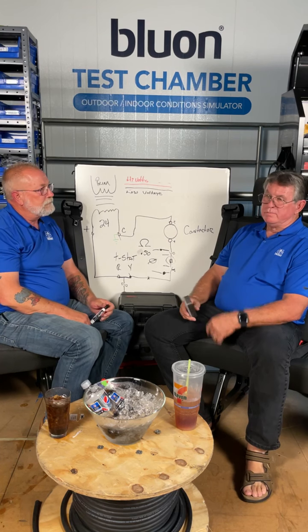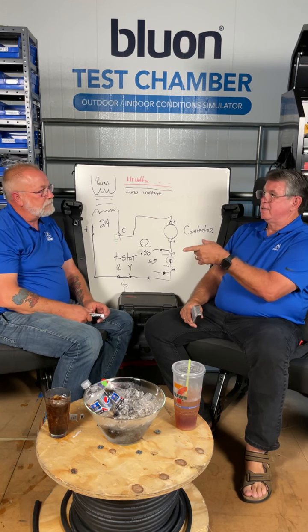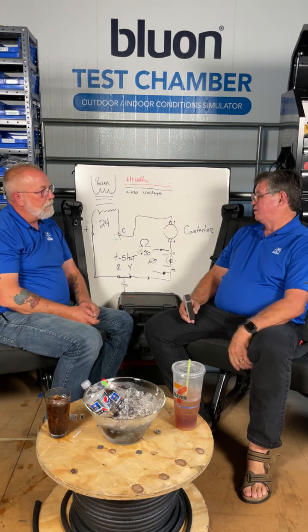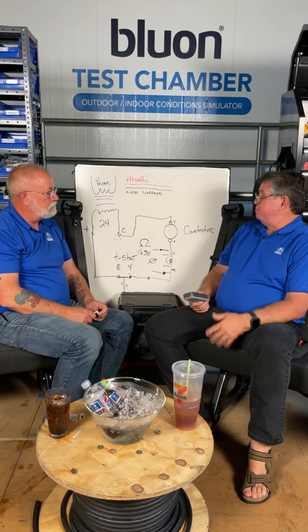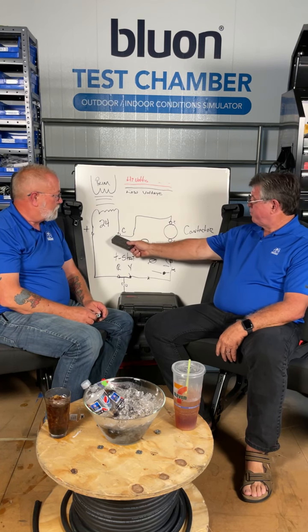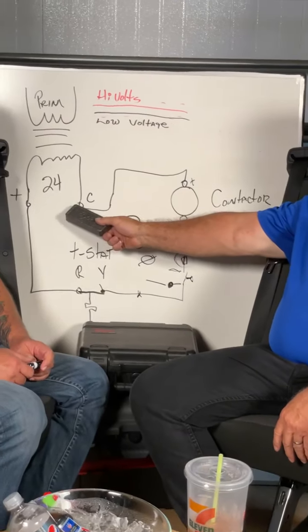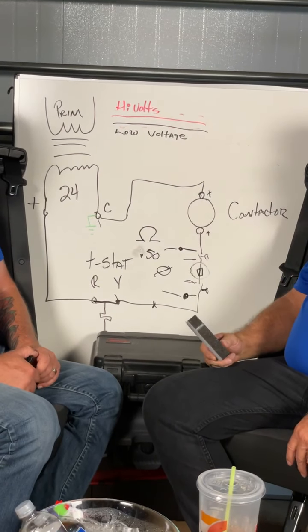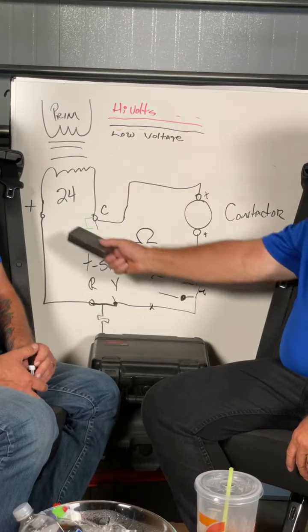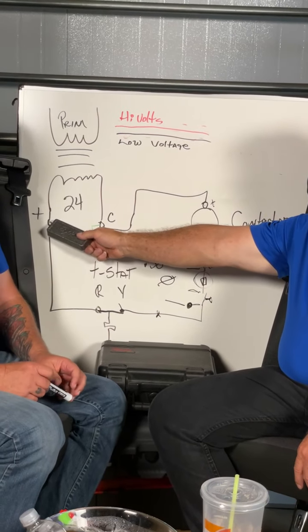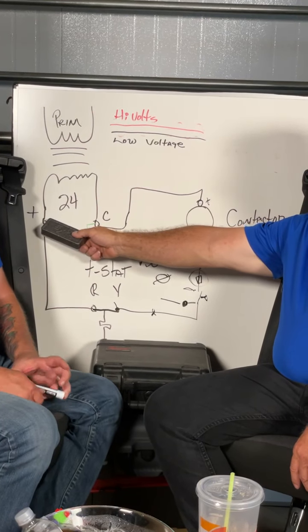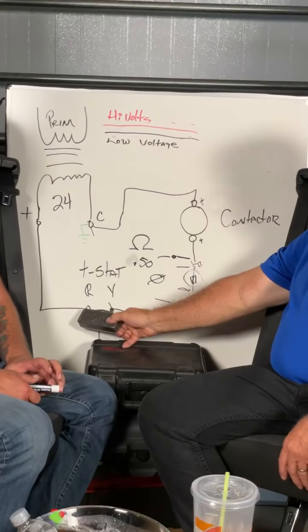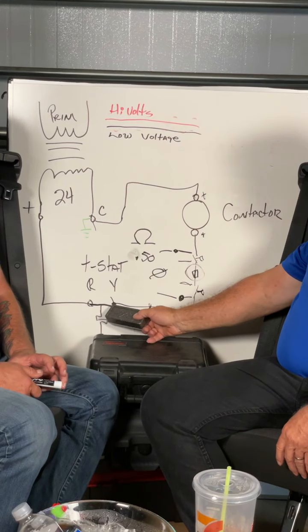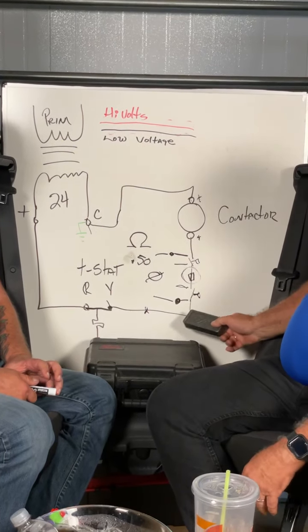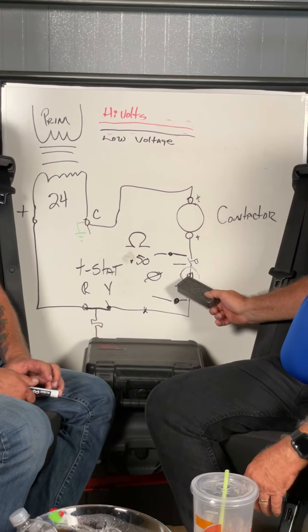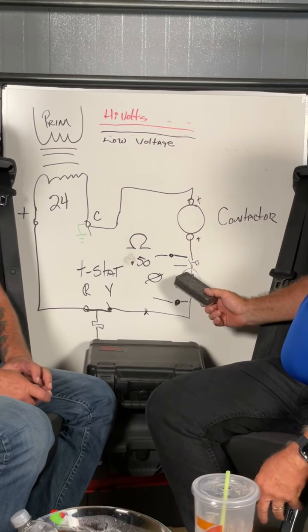Yeah. Now, Brian just attacked this one with ohms or continuity. I like voltage. So if I turn around and go over here and hook my common leg of my multimeter, that would be the black one, and I go to here with the red one and I've got 24 volts. Now I can come down here, I've still got 24 volts. I come here, I still got 24 volts. I get up here, I got 24 volts. I go to the other side and now I've got 0. I just found where my open is at.